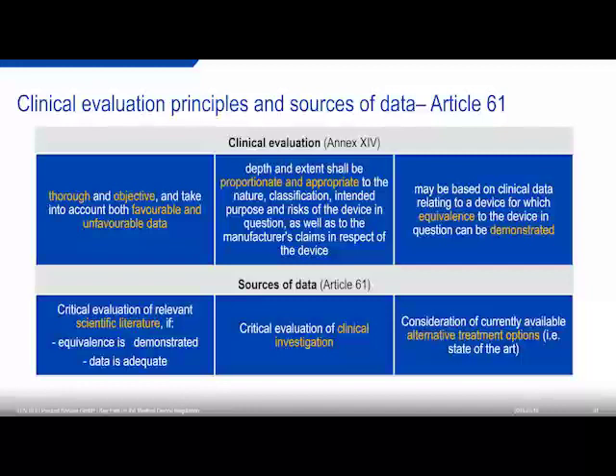So the clinical evaluation in accordance with Annex 14 is thorough and objective and takes into account favorable and unfavorable data. So if you have clinical data about your device that is unfavorable, you have to take it into consideration, and it will be part of your clinical evaluation. Its depth and extent shall be proportionate and appropriate to the nature, classification, intended purpose and risk of the device in question.